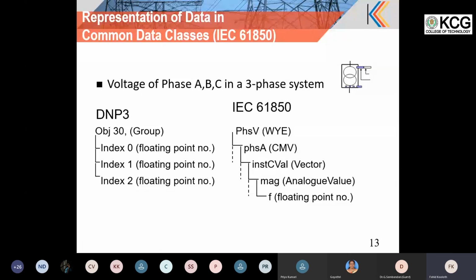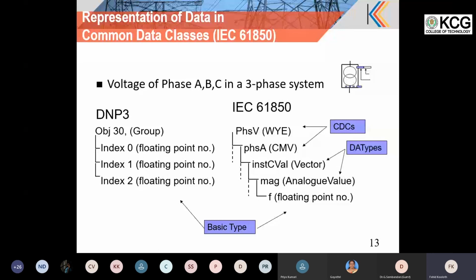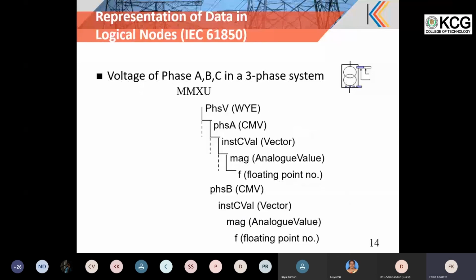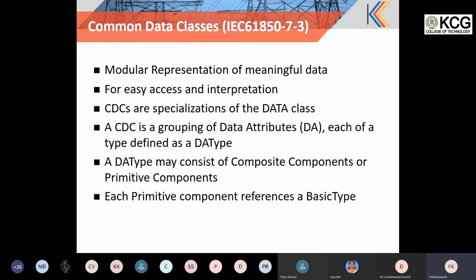Basic type, this is a common data class, complex common data classes. This can have data attribute types, which can have basic types also. So this is the clubbing of data to achieve a functionality. There can be simple data elements grouped together to have a common data class in 61850. So this is another scenario in which basic types are there, then common data classes are there, and these are data attribute types that can be analog data, vector, everything can be there. Then common data classes: this is a modular representation of the meaningful data. It is for easy access and interpretation. This can be constituted of data attributes, for each different data attribute type.